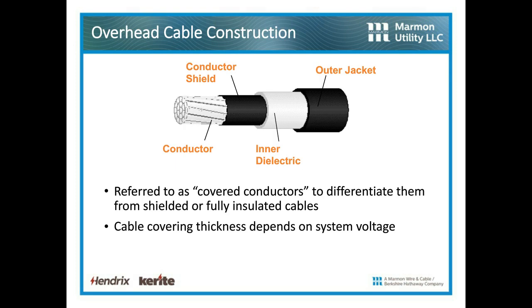The construction basically consists of 3 layers. We first use a semicon over the bare conductor. The semicon smooths out the electric fields when we're in contact with the ground plane. The inner dielectric is a soft, high molecular weight polyethylene that has a great BIL and AC withstand voltage. And importantly also, it's very soft, so that when we do cable stripping it makes it much easier to strip that jacket to make taps.